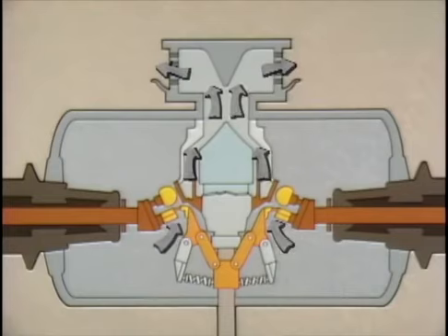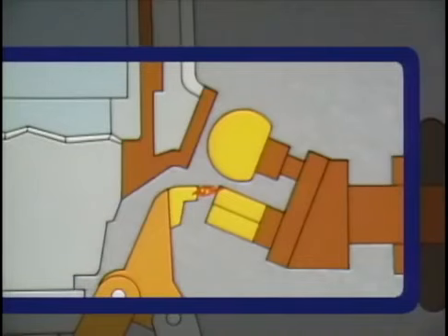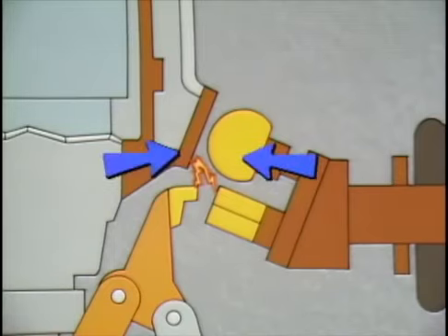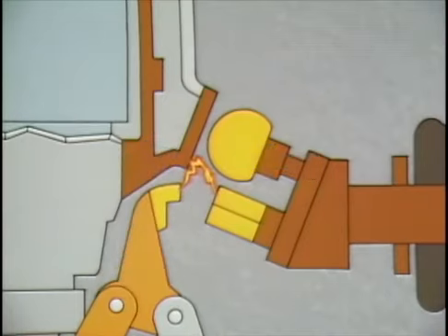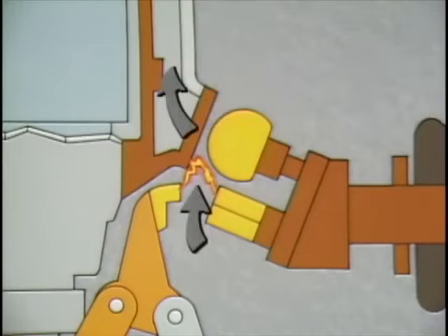to atmosphere. The blast of air helps cool the arcs and at the same time forces the arcs away from the arcing contacts and toward arcing probes and arcing rings. An arcing probe and arcing ring are conductors that help carry the arc away from the contacts. As the contacts continue to separate, the distance between the contacts becomes greater than the distance between the arcing probe and arcing ring.